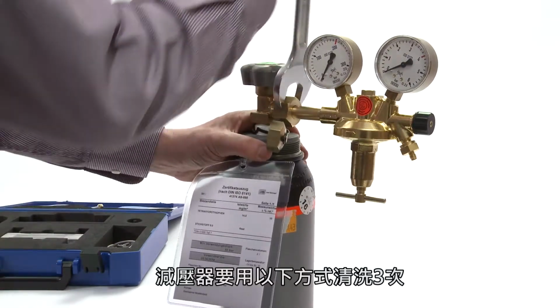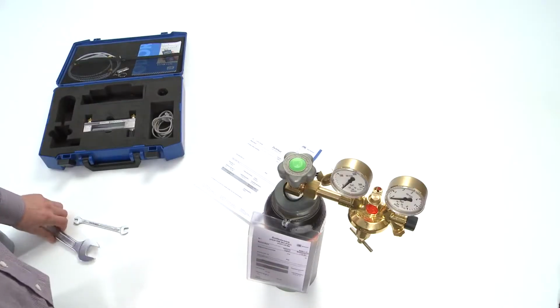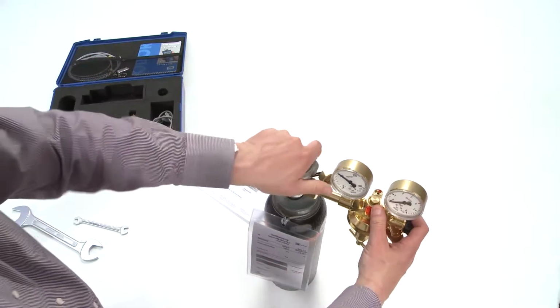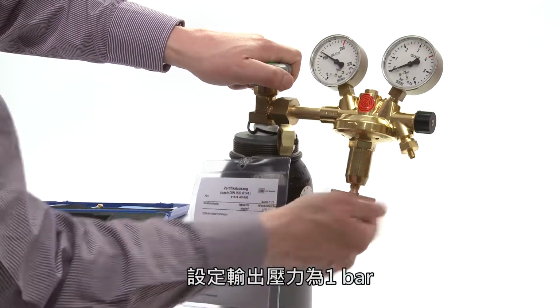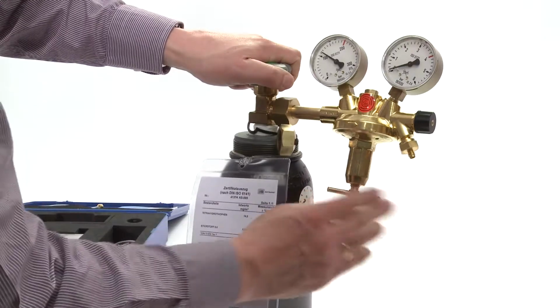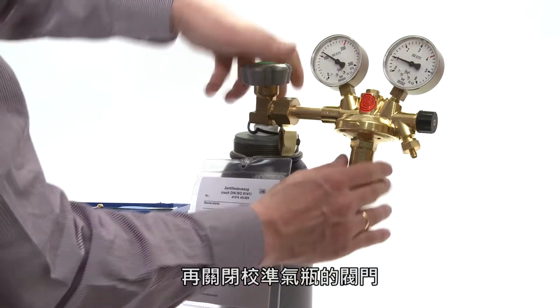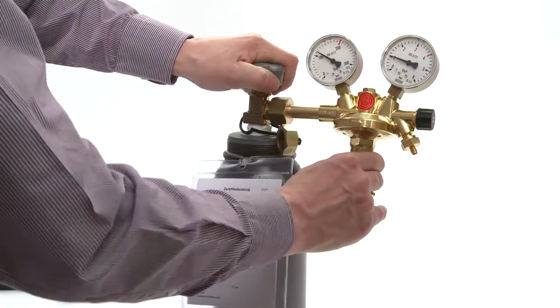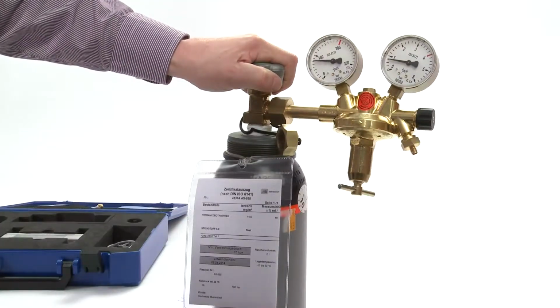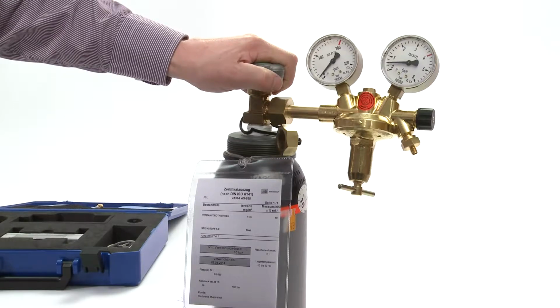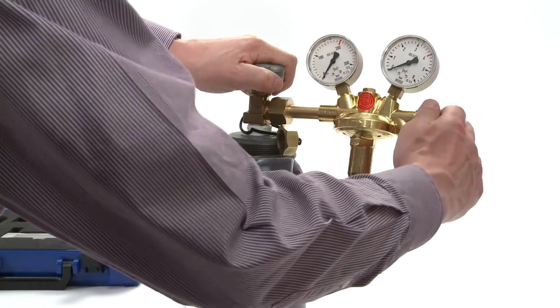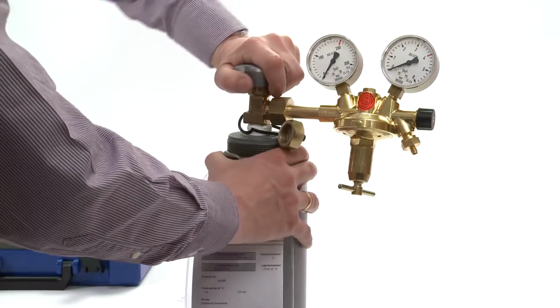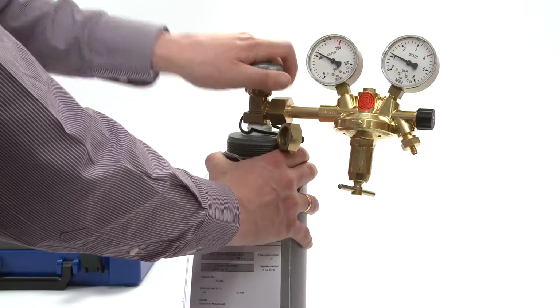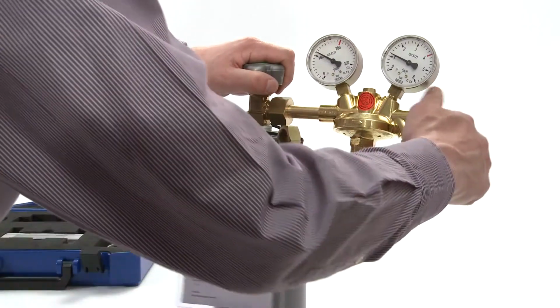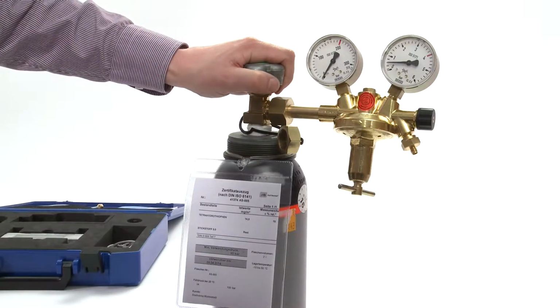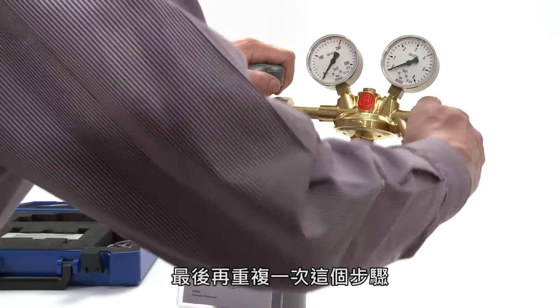The pressure reducer should be purged 3 times in the following manner. Open the calibration gas bottle valve. Set the output pressure to 1 bar. Close the calibration gas bottle valve again. Empty the pressure reducer. Repeat the procedure. Repeat the procedure one last time.